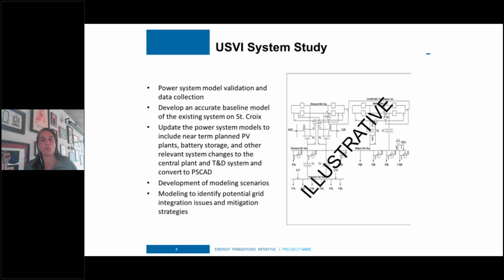So in order to support that, we have been working with them to conduct a system study so that they can best integrate these new technologies. As part of that, we, with one of our national laboratories, the National Renewable Energy Laboratory, had plans to have a team go down, work with the engineers at the utility to install equipment so that we could do significant data collection by running a number of transient events. Well, that was put on hold because of COVID and the inability of people to travel. So what we were able to do is ship the equipment to the utility, and through remote connection, worked with the engineers to install that equipment.